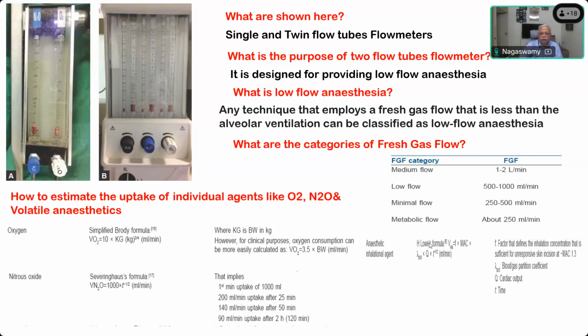And for anesthetic agents, we use what is called the Lowe formula, where fresh gas flow relates to the MAC factor that defines the inhalation concentration sufficient to prevent response to skin incision at MAC 1.3. The blood gas partition coefficient, cardiac output, and time are all taken into account. At least remember the names: Brody for oxygen, Severinghaus for nitrous oxide, and Lowe formula for anesthetic inhalation agents. Even if you don't remember the details of how to calculate, just remember the names, so in case the examiner asks you, you can always answer.